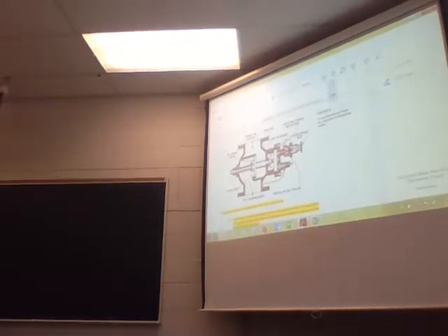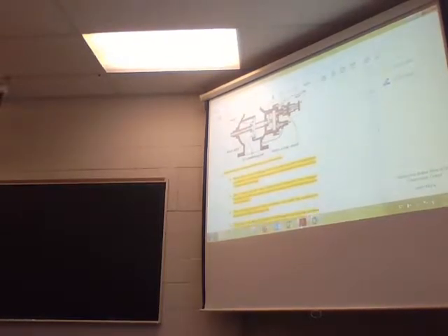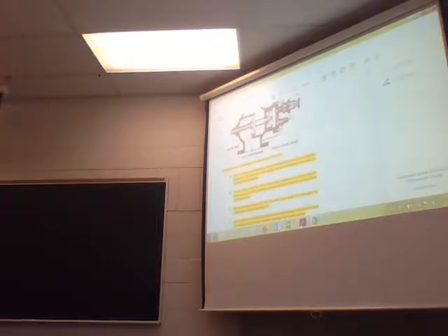And the motor is running continuously. Constant speed all the time. There are several advantages to this type of unloader. Advantages, that's a good thing. With the suction unloader valve closed, the power consumption is minimal. We're not drawing in any air. Kind of cool. The only power required is needed to overcome friction of the machine.